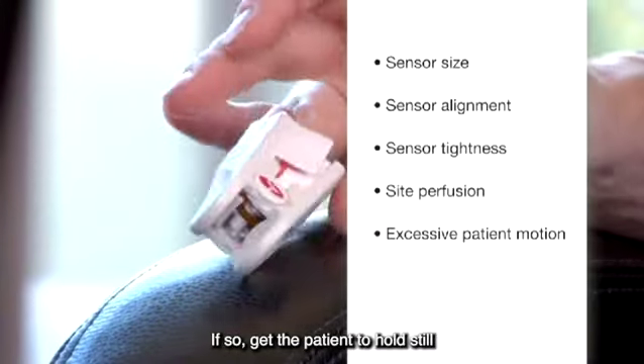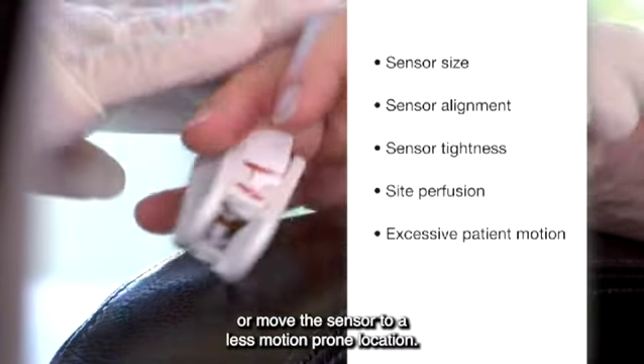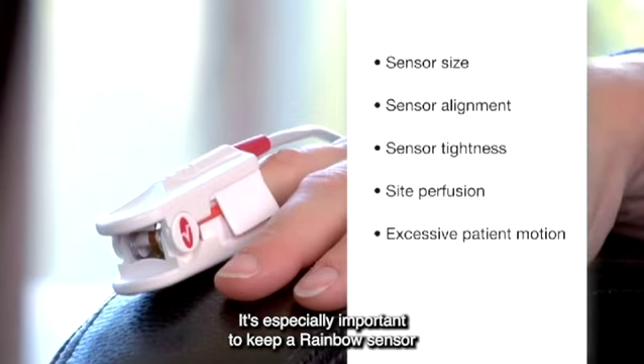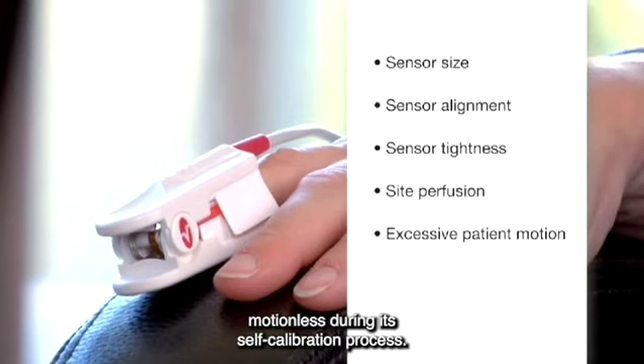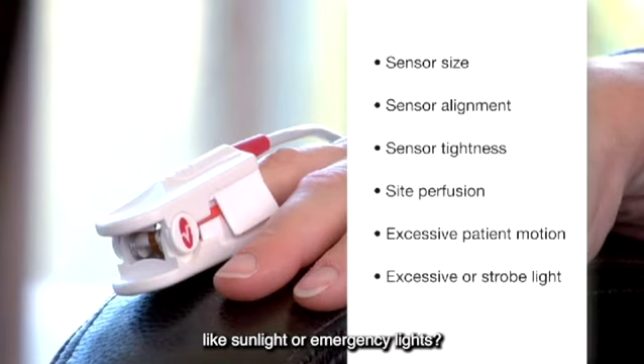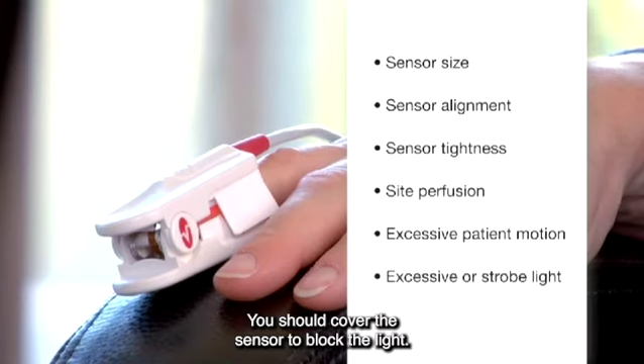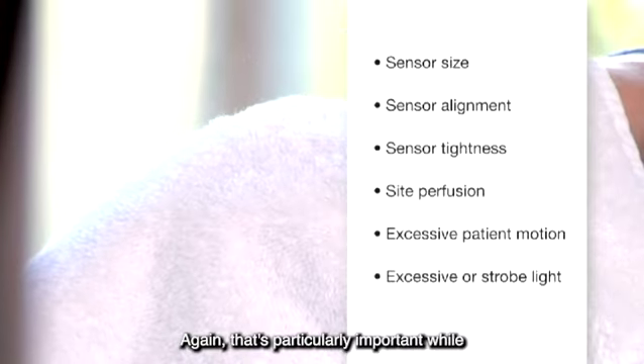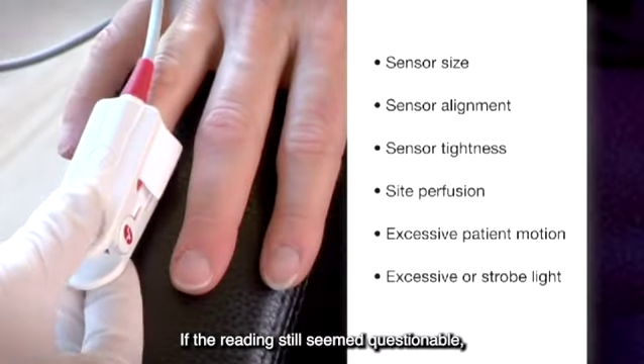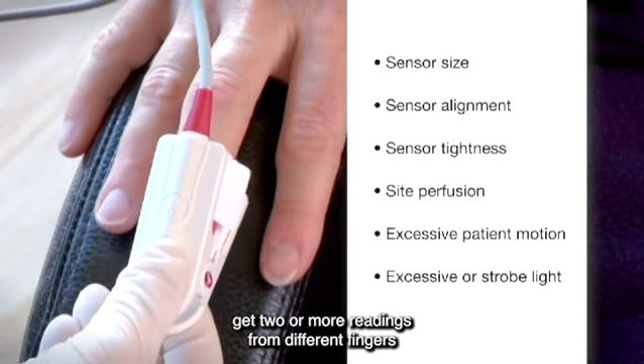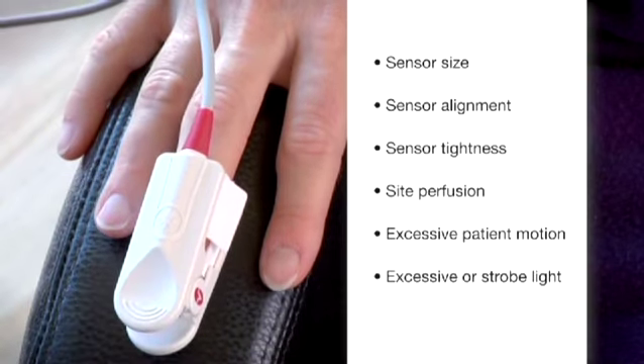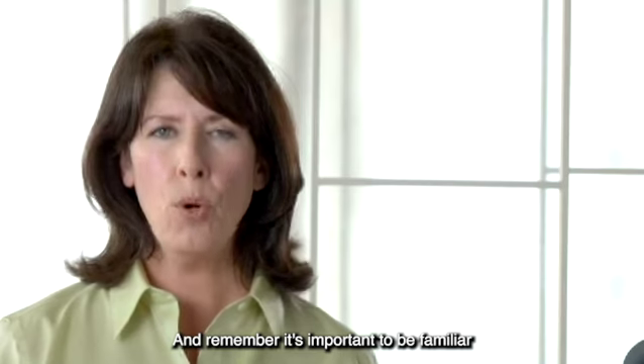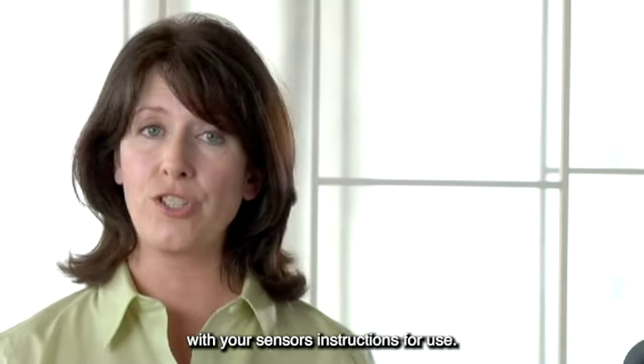Is the patient moving excessively? If so, get the patient to hold still or move the sensor to a less motion-prone location. It's especially important to keep a rainbow sensor motionless during its self-calibration process. Is there interference from bright lights like sunlight or emergency lights? You should cover the sensor to block the light. Again, that's particularly important while a rainbow sensor is self-calibrating. If the readings still seem questionable, get 2 or more readings from different fingers and average them. And remember, it's important to be familiar with your sensor's instructions for use.